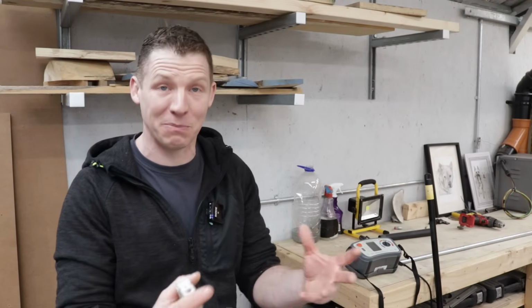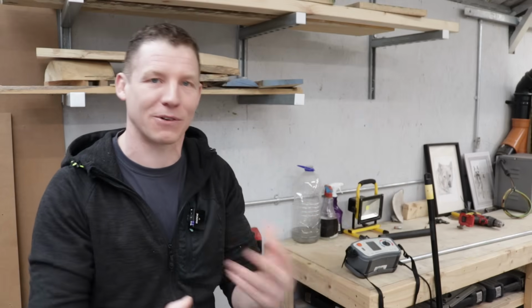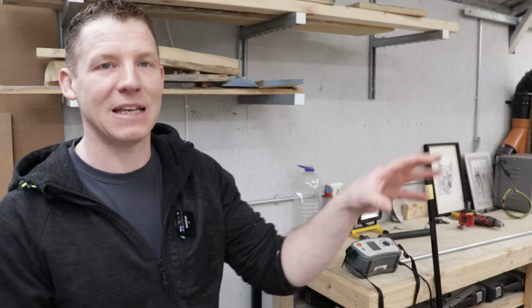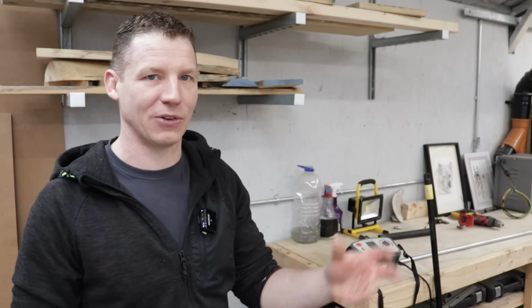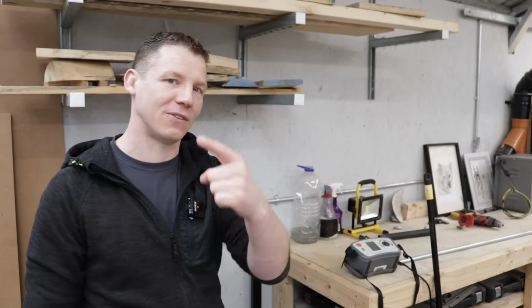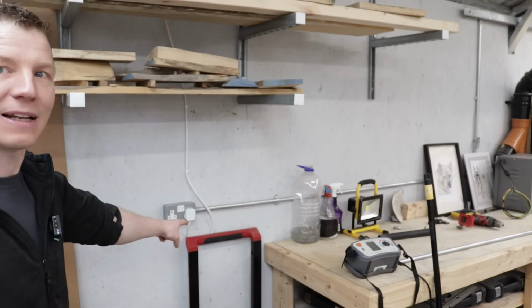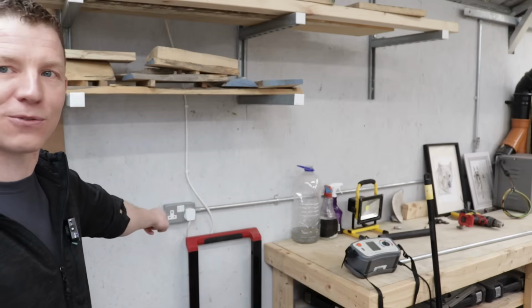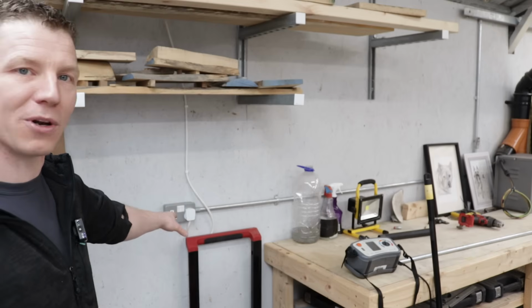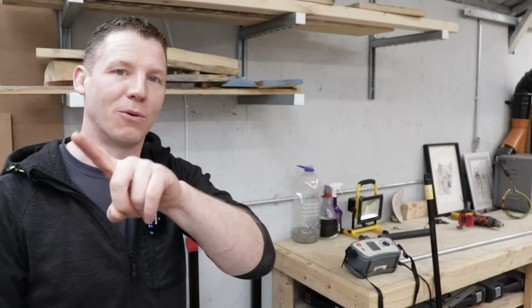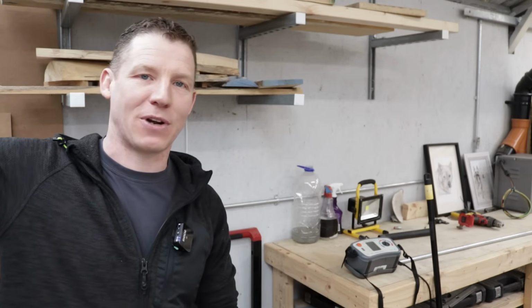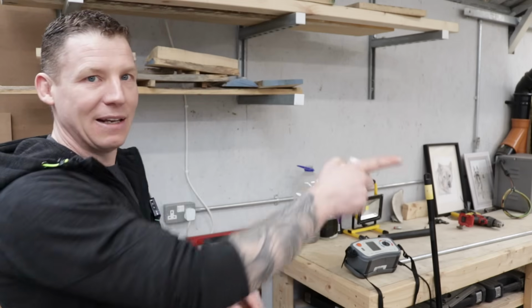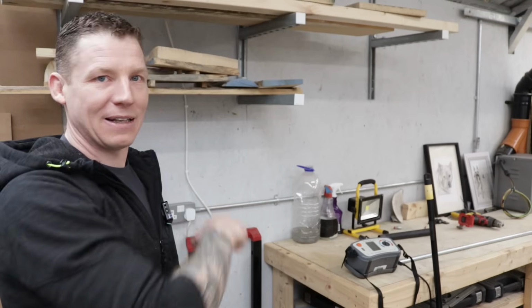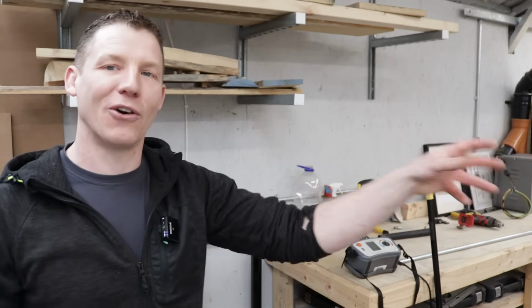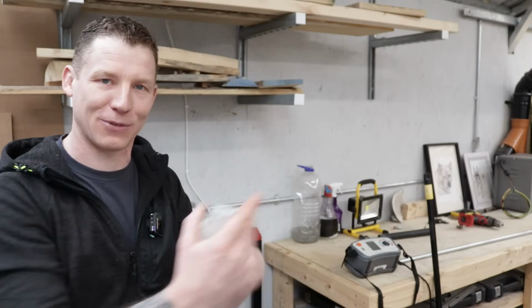Okay, so let's tie this whole thing together about fault loop impedance, what I've been talking to you guys about since the start of the video. And it's important when it comes to designing your electrical circuits or having a conversation with your electrician. They will understand this about keeping circuits short, keeping cables oversized. It's not just the load, it's also the fault loop impedance, which means the total resistance of that circuit, like I said. So we're standing here because that's my furthest socket. That's the longest distance run from my fuse board or from my sub board in my workshop. So it goes back from this socket all the way to my sub board, to the one in my house, and back out to the transformer from my electricity supplier and back in again. It's that total run of that circuit in and out that I will be measuring now in a second, and I'll show you why that's important. And it ties into the whole extension lead thing as well, and the design of electrical circuits. So that's why I'm kind of harping on about this.